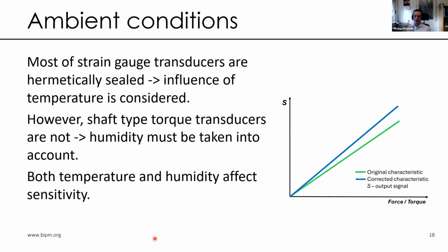In torque, it is very common to also take into account humidity effects, because shaft type torque transducers, which are being applied, are not hermetically sealed. It's just not possible. So both temperature and humidity effects can affect the sensitivity. This is just an example of how we try to correct if the result is being performed at different temperatures or humidity values. Then we have to correct the result based on the sensitivity factors. So that was just the introduction to the principles and effects that we consider in force and torque key comparisons.